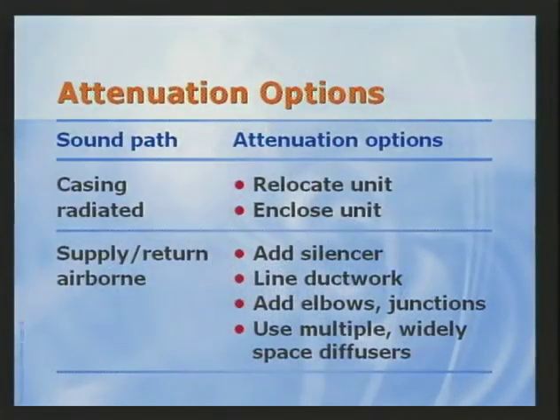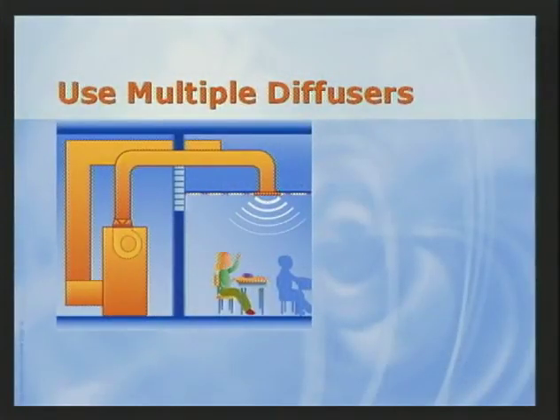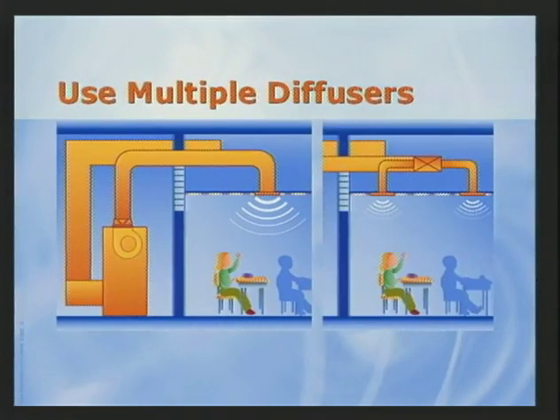Duct elbows and junctions can also be advantageous, provided that duct velocity is kept low. Elbows cause reflection, which reduces the amount of sound traveling down the duct. Junctions split the sound in proportion to the division of airflow. If one diffuser is used, all the sound traveling down the supply duct comes out that diffuser. By putting a junction in the duct and using two diffusers, half as much sound comes out each diffuser. Remember that sound naturally diminishes with distance, so to take optimum advantage of the junction sound split, spread the diffusers as far apart as possible.